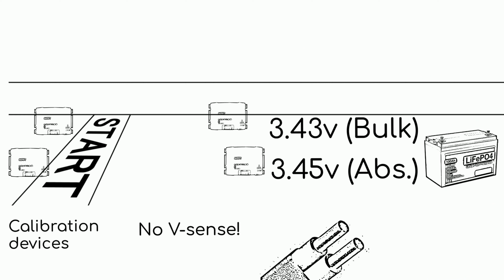For example, the transition voltage to the absorption mode is 3.45 volts per cell, and 3.45 volts is the start point for the cell balancing mode. One of the chargers has switched to absorption mode, and the second is still in bulk mode. Charging current is still high and the balancing process is not effective.